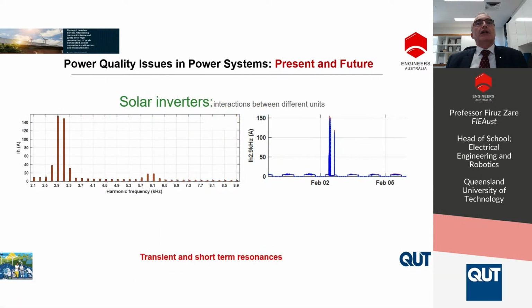Just to focus on that specific case, if you look at this measurement, each pulse sector on the right-hand side, this blue diagram, basically shows one day of measurement. When the current is 0, it means during the night the solar inverter is switched off, and the other one is during the day. That specific frequency, 2.9 kilohertz, looks very stable for a couple of days, except on the 3rd of February, when you see significant resonances happen for a few hours.